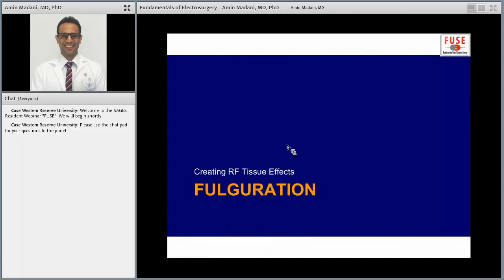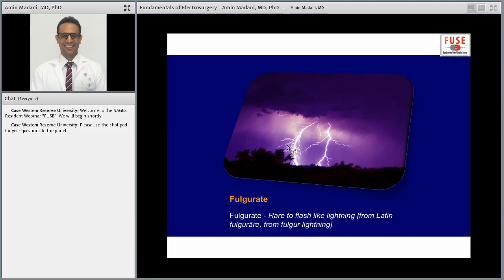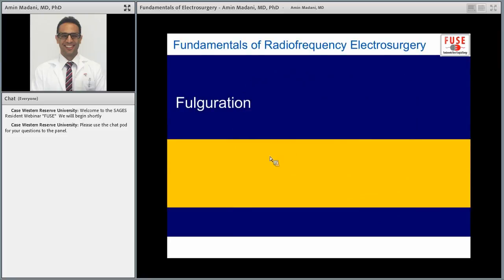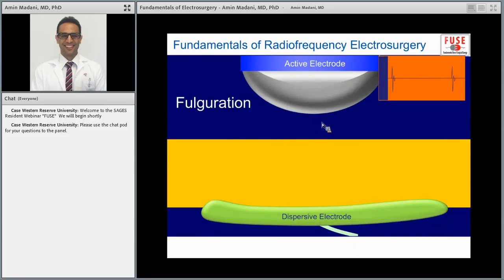So fulguration, this is the last thing I'm going to talk about. Fulguration is basically when you spray current. Essentially, it's a no-touch technique. So you bring the electrode close to the tissue, you activate it. Because it's very high voltage, the energy jumps across, it arcs, and it superficially desiccates the tissue. So just like I previously showed you, it doesn't transmit energy to the tissue below, it spares that, but you get a very superficial area of desiccation, because it's a non-conductor. It doesn't travel below that once it's desiccated.